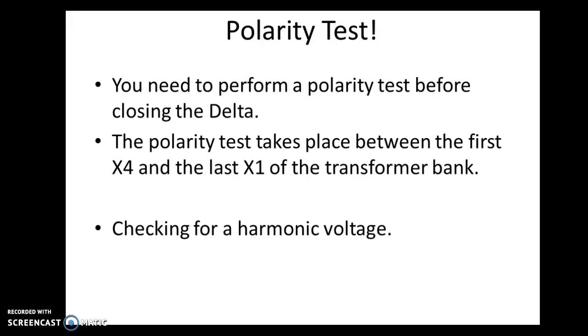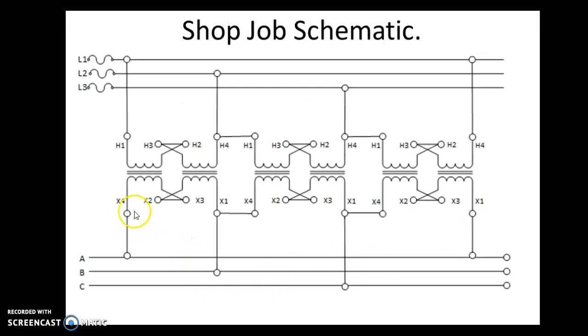The polarity test takes place between the first X4 and the last X1 of the transformer bank. What are we checking for? We're checking to see if there is a real usable voltage. Sometimes you will see a harmonic voltage, which will appear in multiples of the supply frequency. For us, we have a 60 Hertz system. And if it is a real voltage and you connect those two wires together, so if you connect X4 and X1 together, and you measured 120 volts, let's say, that's essentially like placing line 1 to neutral. It would create a dead short, damaging the transformer and in some cases causing an explosion.